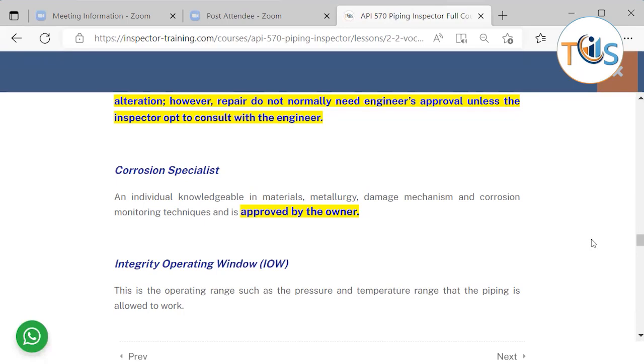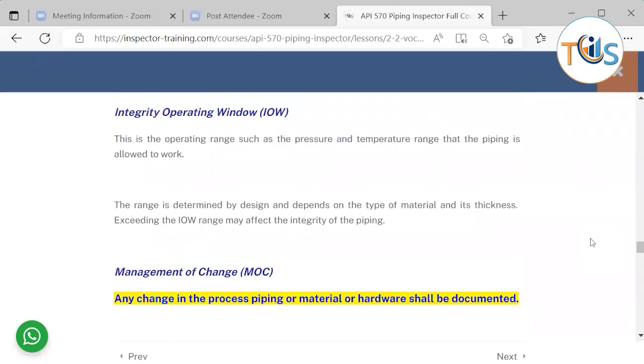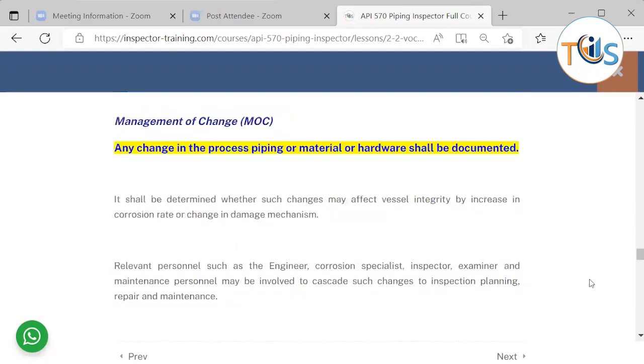The integrity operating window represents the design premises — the design output. Most simply, it is the pressure and temperature range within which the piping can operate, but other parameters such as pH, fluid type, fluid velocity, and other process parameters can also be part of the integrity operating window. This range is determined by the design and depends on the material type and thickness. Exceeding the integrity operating window may affect the integrity of the pipe.